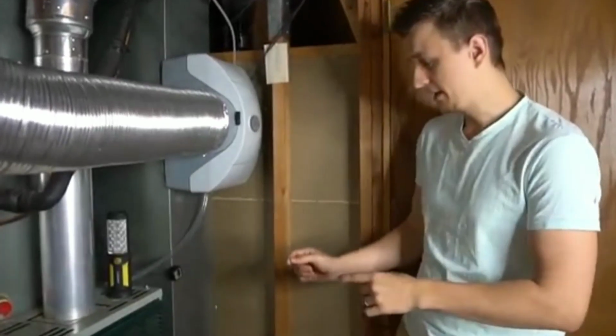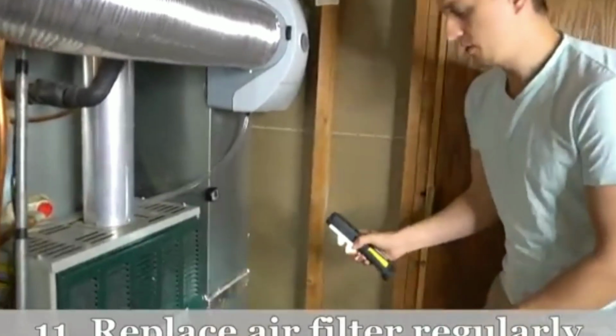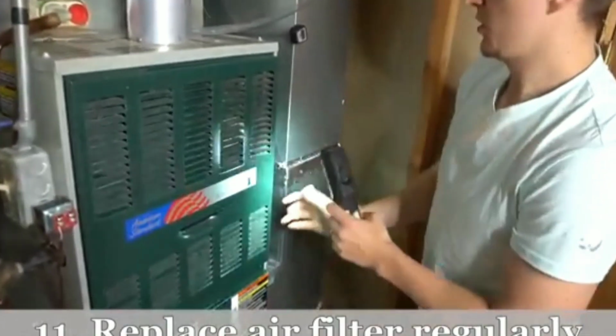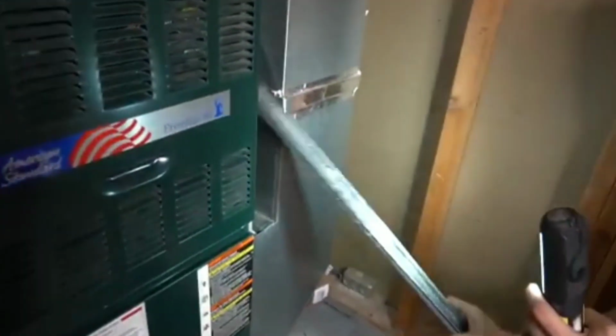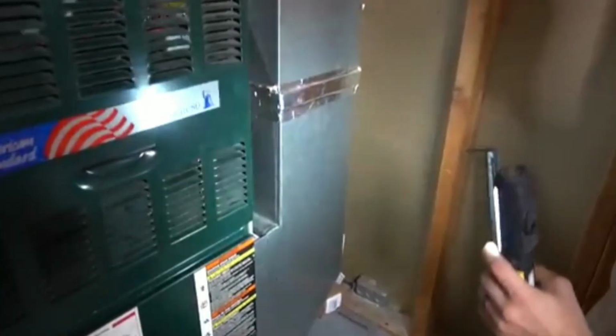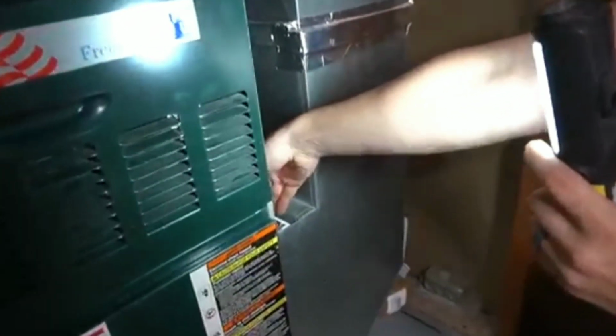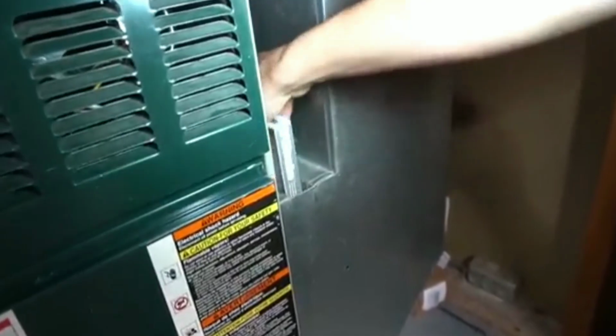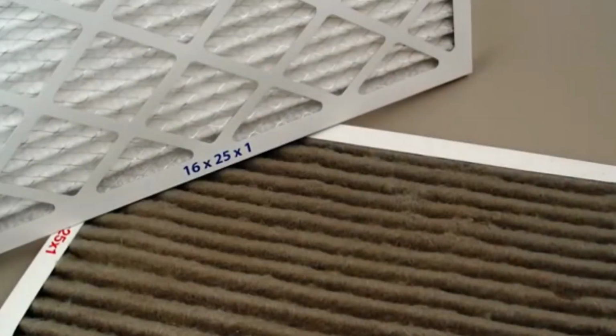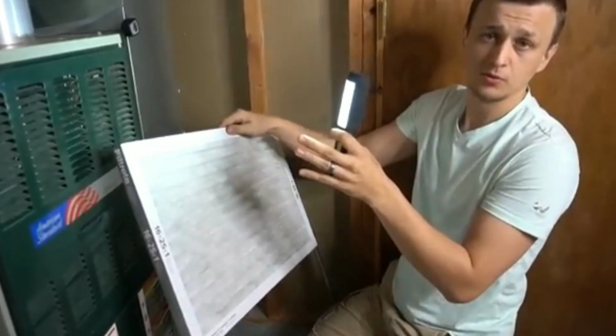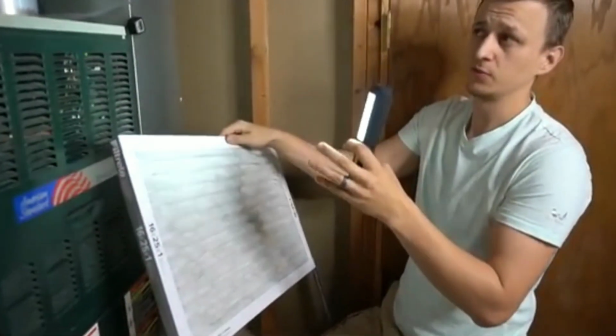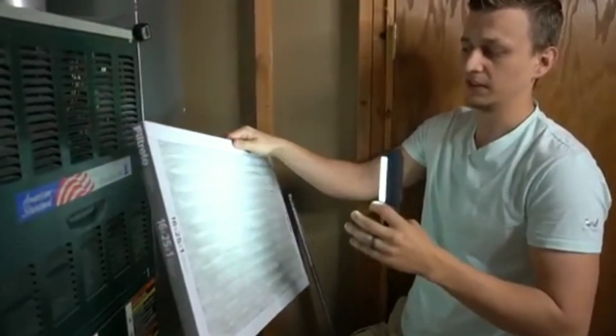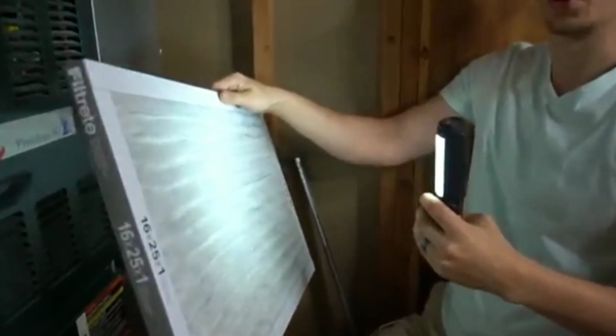So, moving on, maintenance tip number 11 is the furnace filter. Even though that sounds like common sense, it actually is one of the most neglected things. I think that was furnace problem number 2 out of the most common furnace problems. And for AC, that's a pretty frequent problem as well. If this filter gets really dirty, it'll have the same effect as the coil being dirty. So that'll affect the refrigerant pressures or the freon pressures. And your coil can start to freeze up, or basically it's not going to keep up with the hot air, or it's not going to cool your house enough.